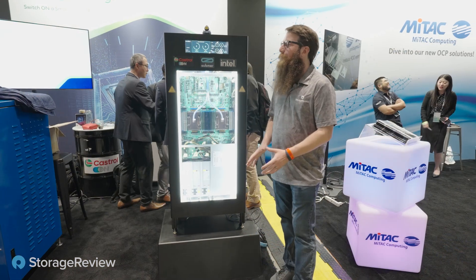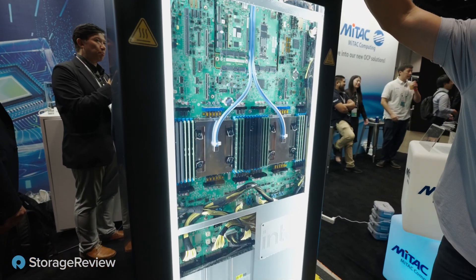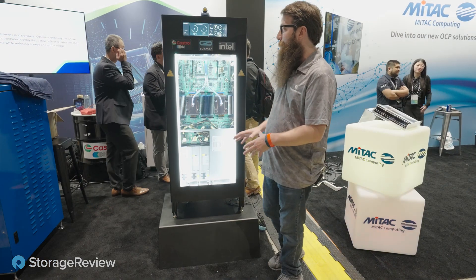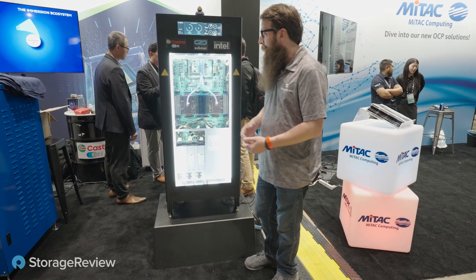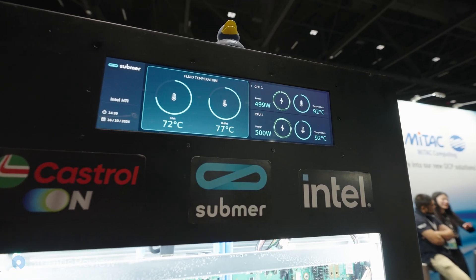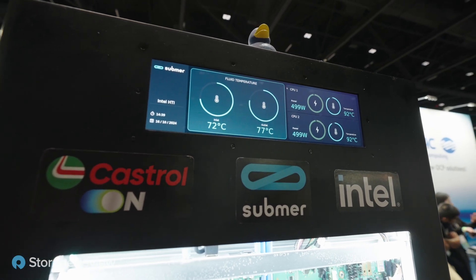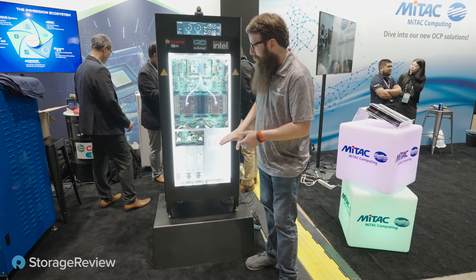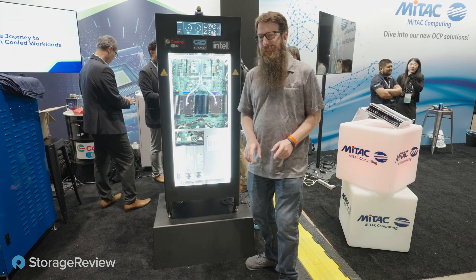Our old friends Castrol over here — they partnered again with Submer to create one of these amazingly beautiful immersion tanks. Submer really has the talent to make these things eye-catching. They've got a high-power, high-temperature system here for dual Intel Xeon — the fluid inlet is at 72°C, the outlet at 77°C. They're running the CPUs at about 500 watts each, well within their limits. Really cool stuff — they've also got a Grace Hopper over there, so let's take a look at that as well.